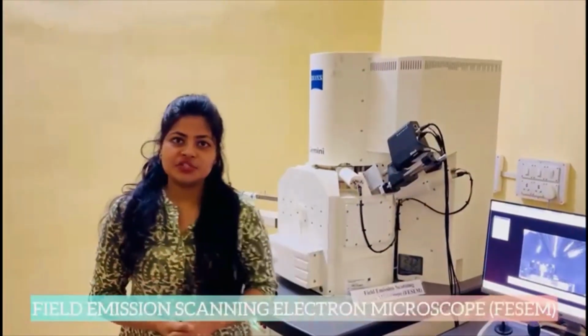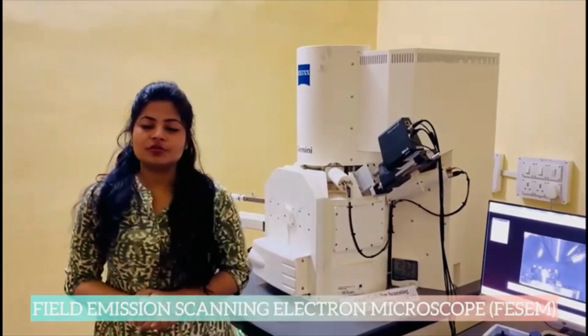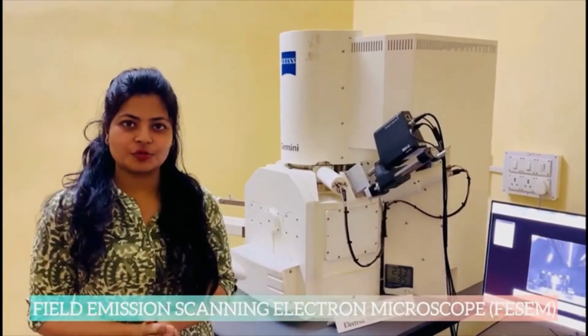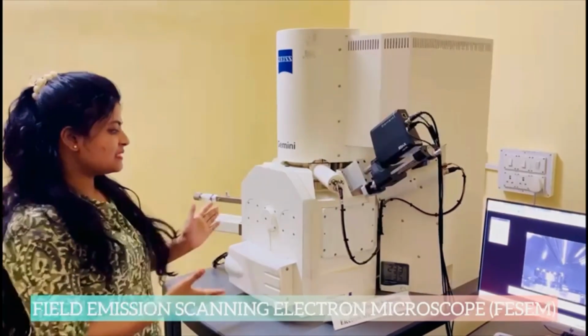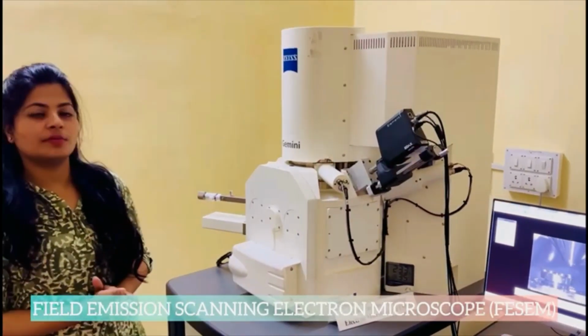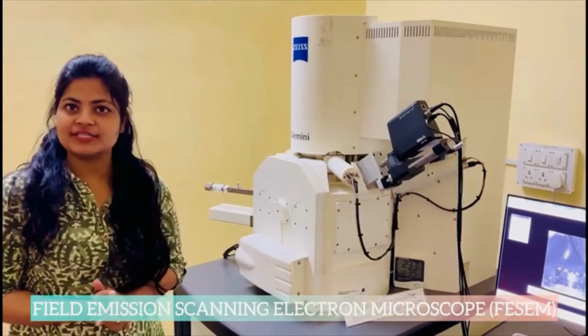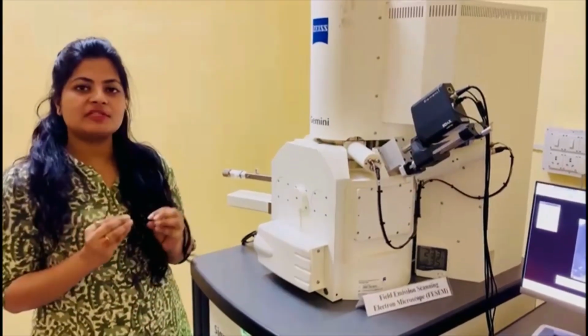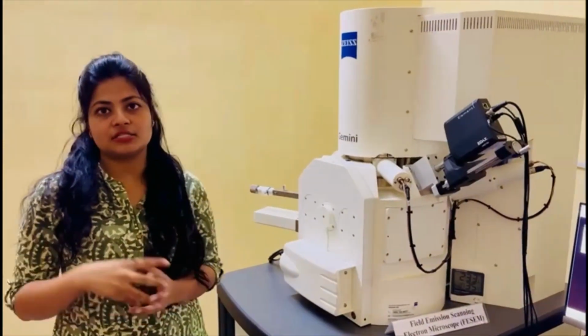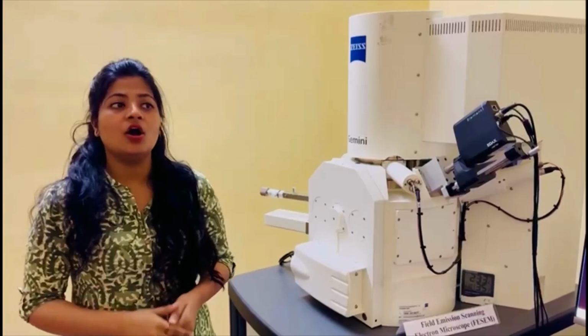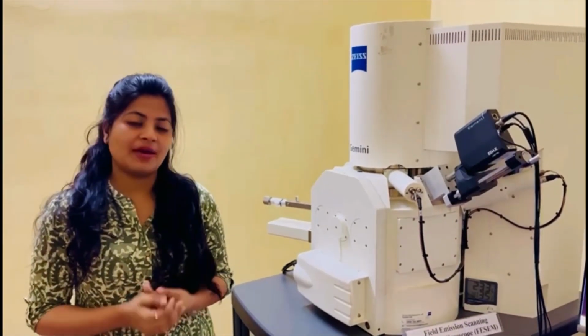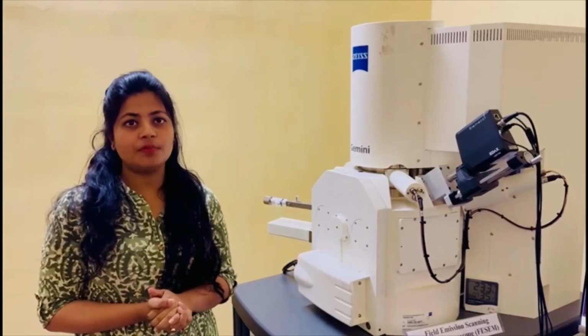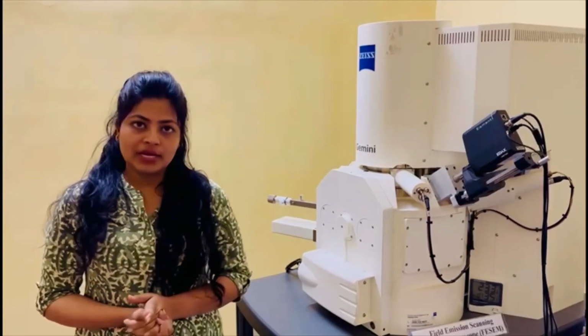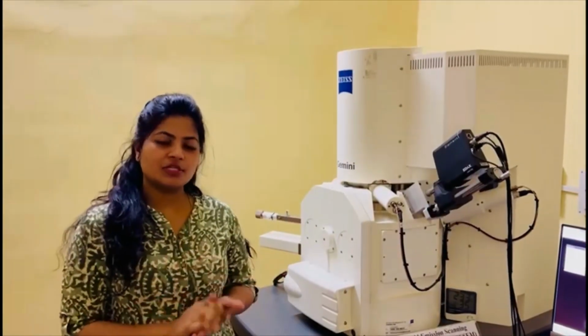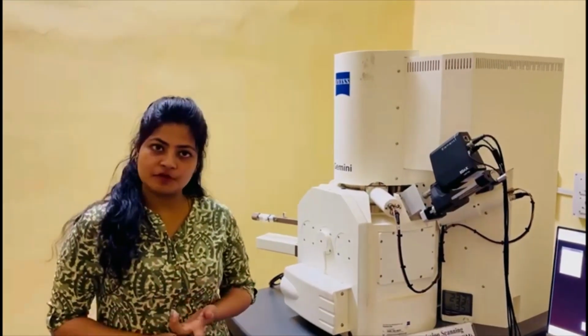So our last machine is FESEM, also known as Field Emission Scanning Electron Microscope. The one you're seeing is made by Carl Zeiss, Germany. The model is Sigma 300. The major specification of this instrument is the resolution, which is approximately equal to 3 nanometer.